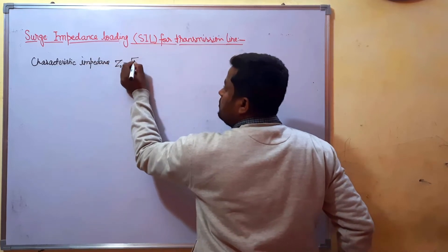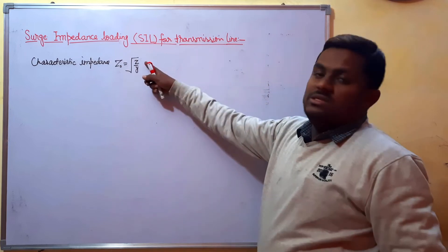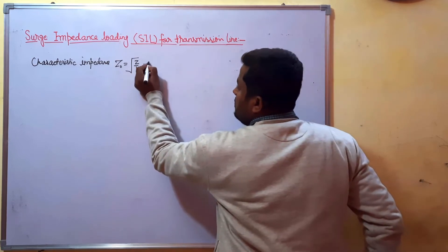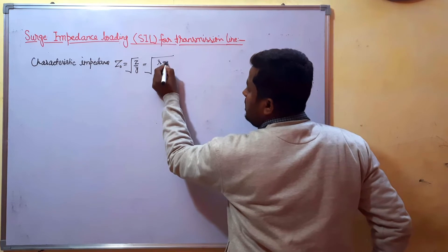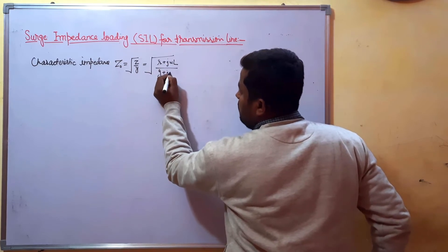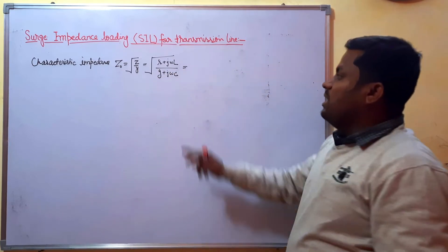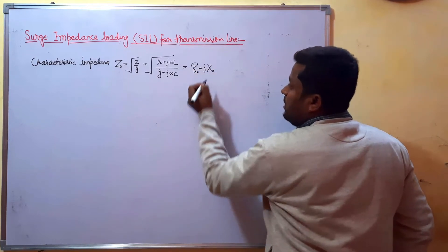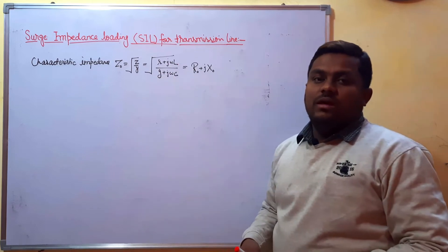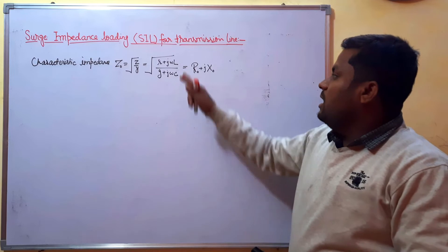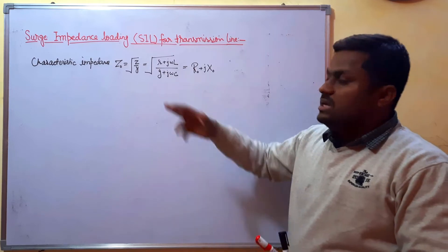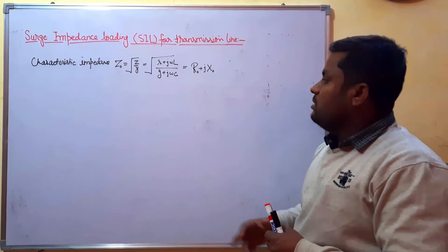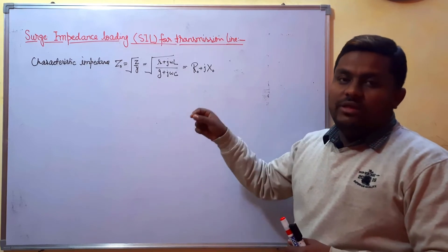The characteristic impedance Z0 is given by Z0 = √(Z/Y), where Z is the series impedance per unit length and Y is the shunt admittance per unit length. This can also be written as √((R + jωL) / (G + jωC)). Here R is the series resistance, L is the series inductance, G is the conductance, and C is the shunt capacitance of the line, all per unit length.